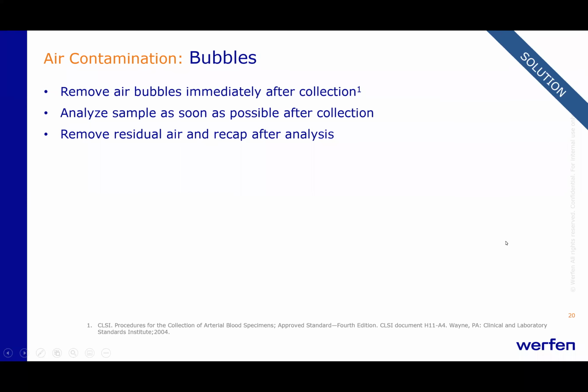So the solution, obviously, remove the air bubbles immediately after collection. So don't just draw the sample and hold the site and set the syringe down uncapped. Always, always, always remove the air bubble as soon as possible. Analyze the sample as soon as possible after collection. That reduces the potential for any air bubble contamination, and remove residual air and recap after analysis. So once a sample is analyzed, always remove the residual air and recap in the event that you would have to reanalyze due to error detection by the analyzer.